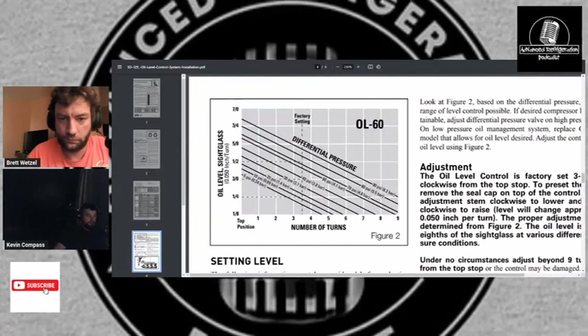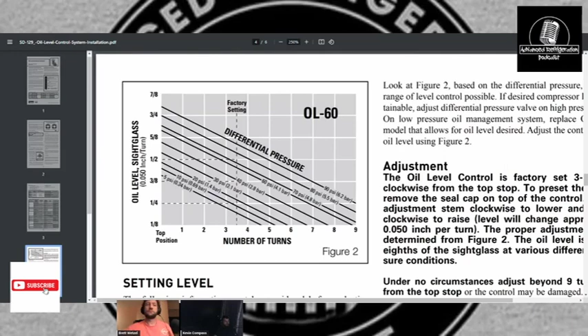You may have a little bit here and there to tweak, but generally when I'm setting oil level controls, I'll set all the rack the exact same way. Like Brett just brought up on here, this is an OL60, OL60 HX, whatever it is. If you look on there, on the left-hand side you have the oil level in the sight glass. On the bottom axis of the graph, you have the number of turns. In the middle, you have your oil differential lines. If you go to a 20-pound differential, say you want a half-inch glass, you're going to be almost half a turn from top dead center, or wide open on this thing, to get that half a glass.